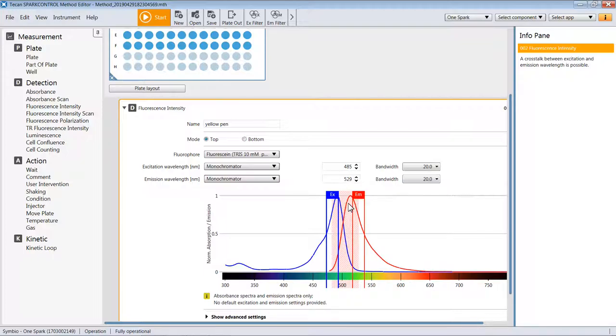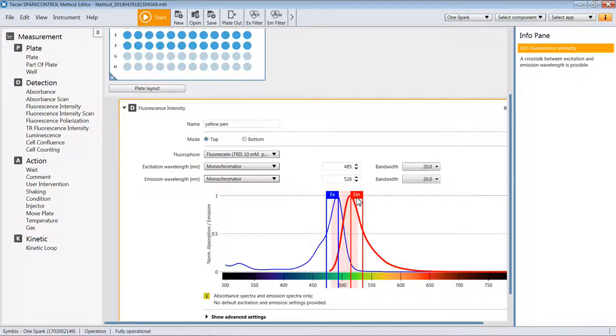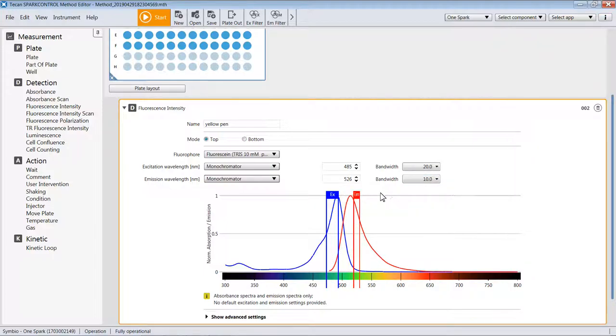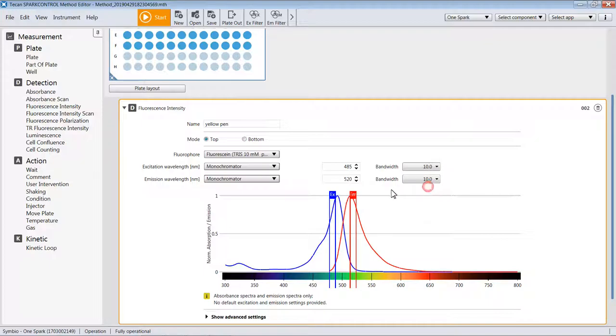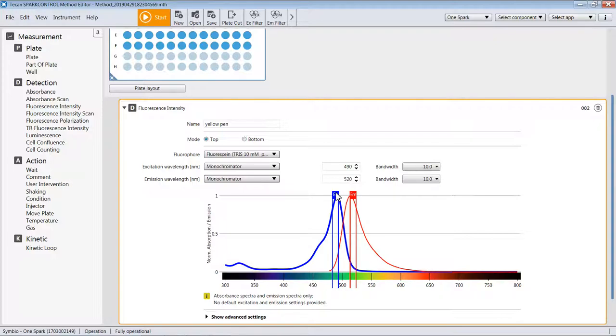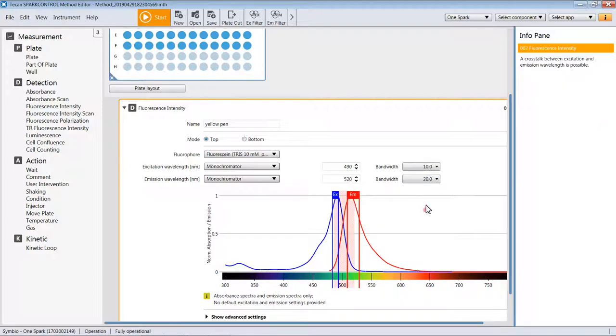Ways to overcome this would be to move the wavelengths apart. But if the dye was such that you wanted to be very close in terms of excitation and emission, you could adjust the bandwidth if you have an enhanced spark. I could reduce it to 10, and this lets me get closer to parking things over the emission. Alternatively, I could reduce the bandwidth on the excitation. As I'm doing this, I am letting less light into the sample and collecting less light back, which could result in some lower sensitivity, but by having narrower bandwidth, you can have a smaller minimum distance between excitation and emission. I'm going to go ahead and back things out to our 20 and 20 again, and get our emission back up to a healthy minimum distance.